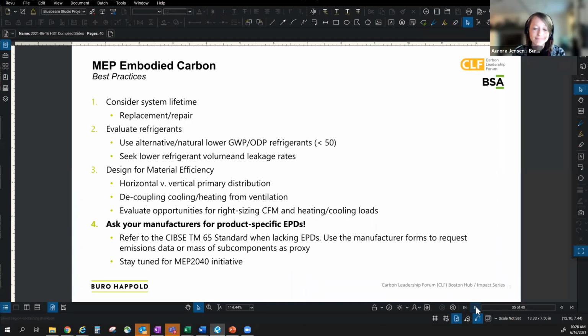Design for material efficiency is nicely represented in the example Jacob just showed. If you examine the difference between horizontal and vertical primary distribution, decoupling your cooling and heating from ventilation - that's not a universally true rule, you could imagine situations where it goes the other direction - but largely, minimizing the size of your air handling units and ducting systems tends to have gains. And then, best practices in operational carbon as well: right-sizing your total airflows and evaluating your heating and cooling loads, taking a hard look at those, can substantially provide opportunities for reduction.